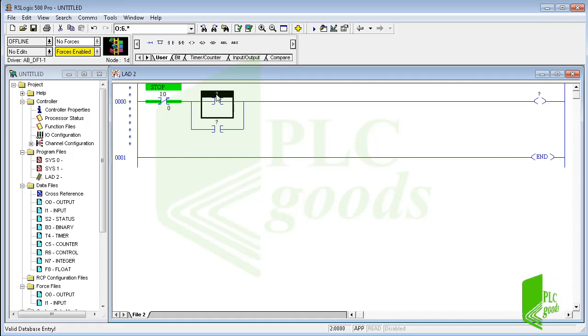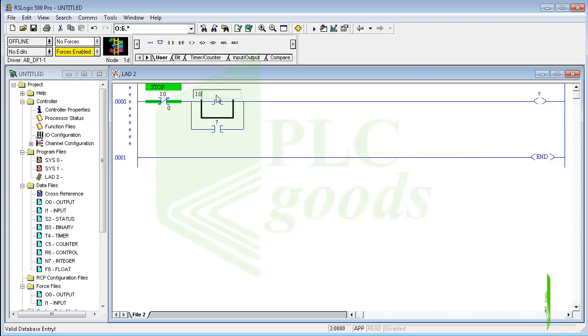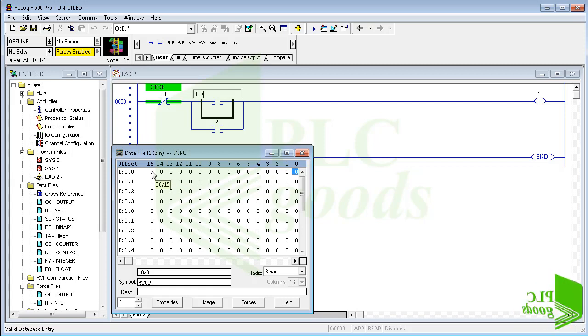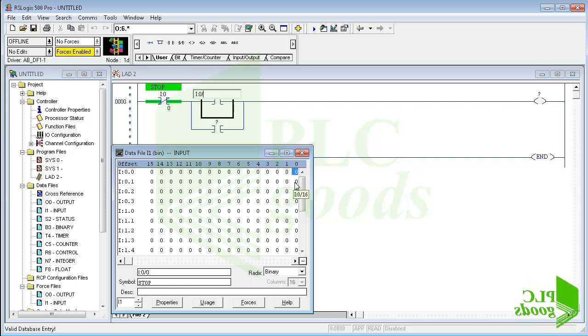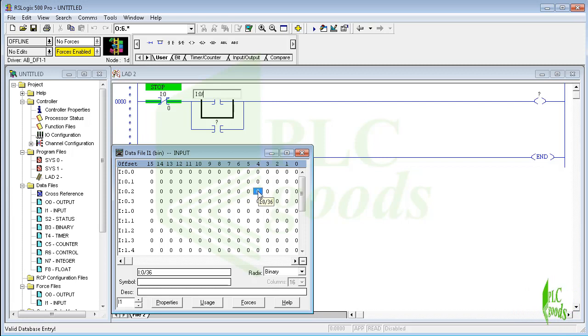I want to use the next digital input to activate the other contact in my program. Let me show you another way for input/output addressing. After I and the slot number, I can enter the overall bit number instead of entering the word and its bit number. In the input image table for each slot number, the first word has 16 bits numbered 0 through 15, and the next word has bits numbered 16 through 31. For example, we can refer to a digital input with its word and bit numbers — 2 and 4 respectively — or just use its overall bit number which is 36.